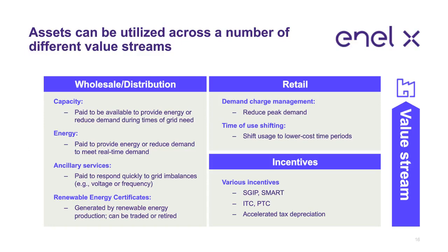And so those are two common types of demand charges that a customer can pay. And then the second big bucket is energy savings. So leveraging your flexibility to shift production from high price times to low price times. The most prominent example being California time of use rates, where they're relatively high, 4 to 9 p.m. in the summer, lower in other parts of the day and year. So it incentivizes when you use your electricity.